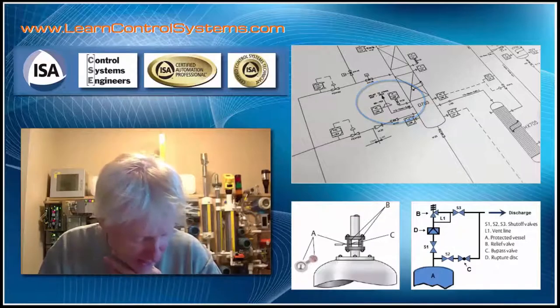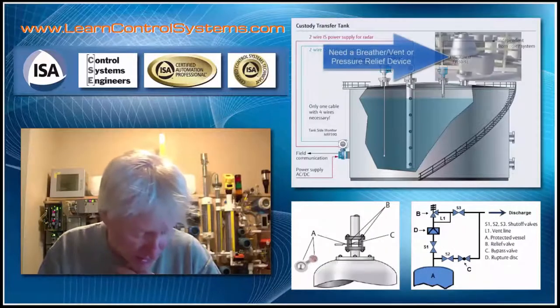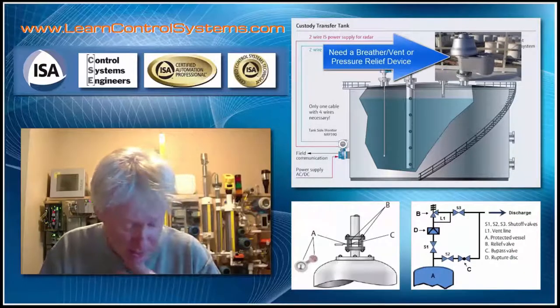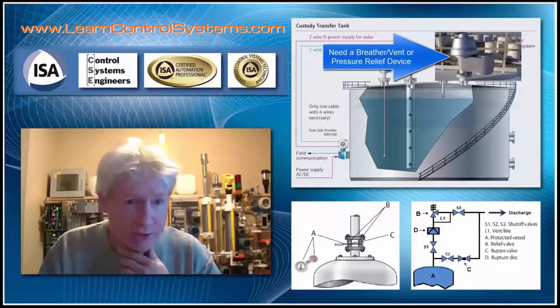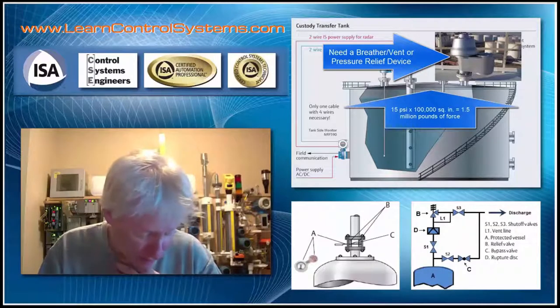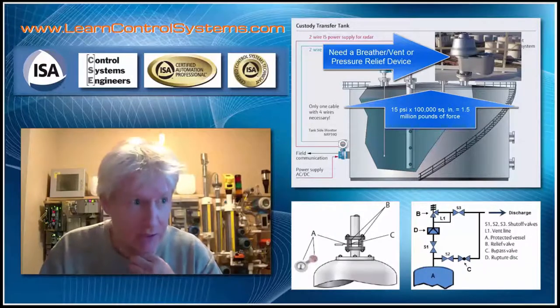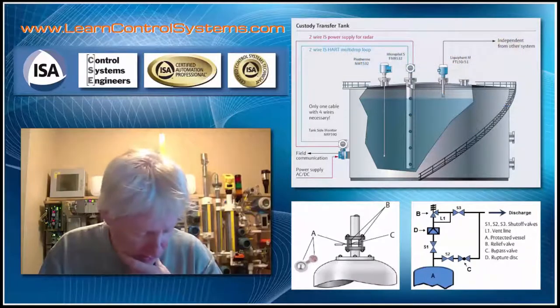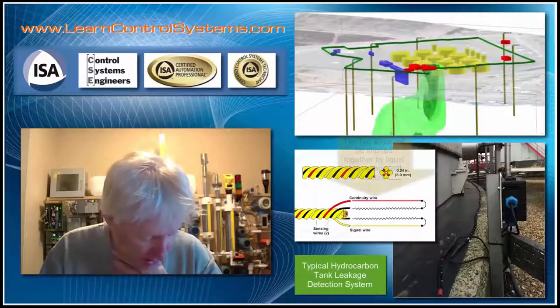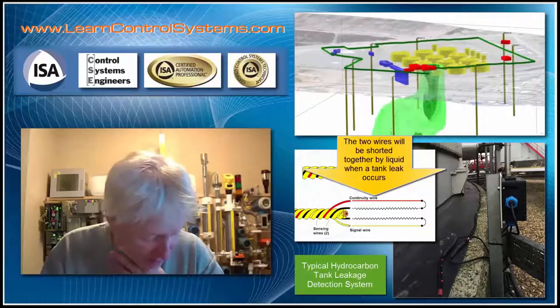We have to understand pressure building up in vessels and pipes — too much pressure from clogs or blockages can cause vessels and pipes to explode and gaskets to blow out. Take 15 PSI times 100,000 square inches and you've got 1.5 million pounds of force — you could blow the top right off a tank. We have to have pressure relief to make sure this doesn't happen, including blow-out protection at the bottom of tanks.